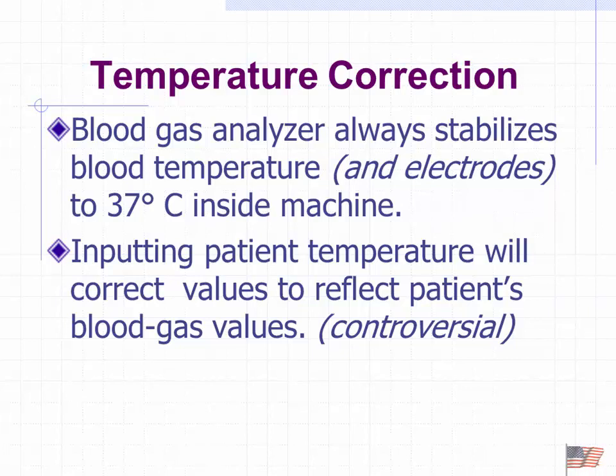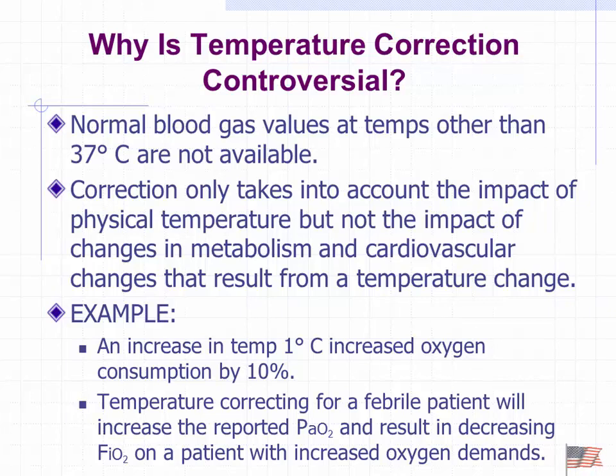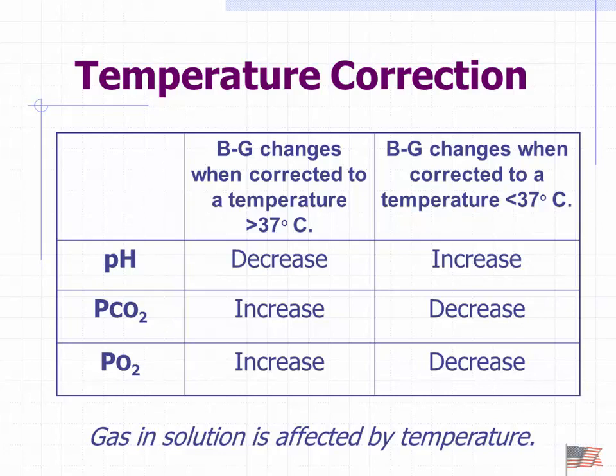Okay, let me talk a little bit about temperature, because temperature is a big effect. We are measuring these values at, in essence, body temperature, 37 degrees Celsius. Inside the machine, that water bath is kept at a constant temperature. What we want to do, though, sometimes is input the patient's temperature to say, well, my patient's not at 37, though. They're at 39. How is that going to affect the results? It only takes into account the temperature of the blood. It doesn't talk about the fact that as you get warmer, as you get a fever, your metabolic rate speeds up, so your CO2 production, O2 consumption changes. And you can see the value there. Don't have to memorize it.